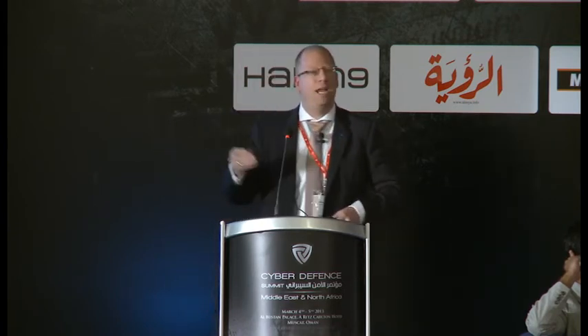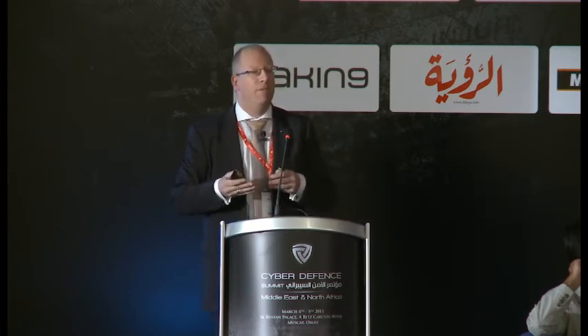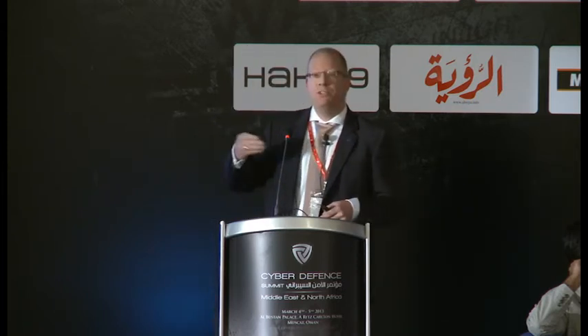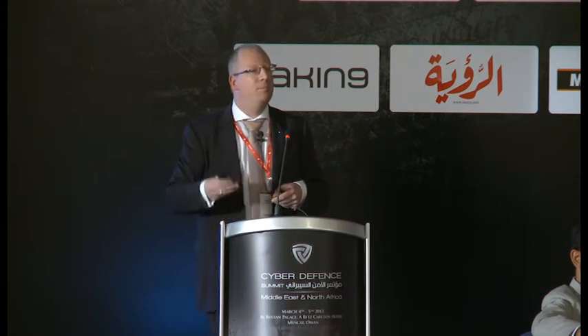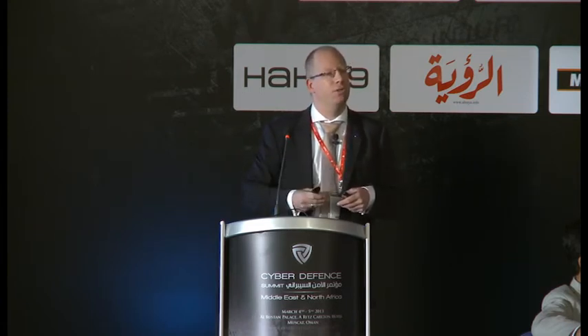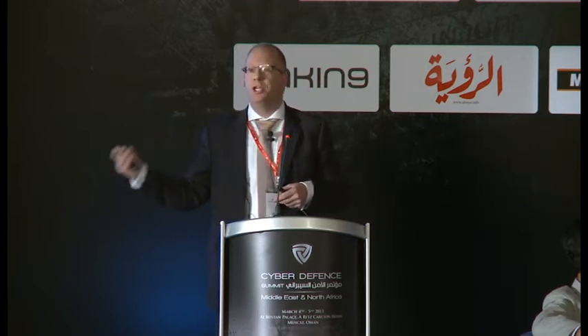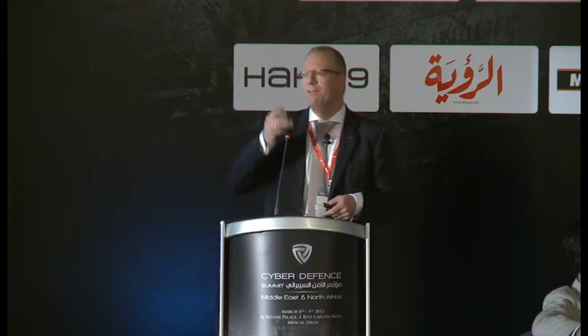There were devices which were failing because you sent them different bits in the TCP/IP protocol, acknowledge, final, and reset at the same time. There were devices failing when you connected to the web server and sent them a string of 8,000 letters. The device, again, had a buffer overflow and was failing. This means, with very simple means, which are not APTs, a very simplistic tool, you can bring down control systems. Bringing down a control system means maybe your control process is still working, but your communication to the control system is completely dead. This is blunder of the vendors, and we were talking about vendors beforehand.